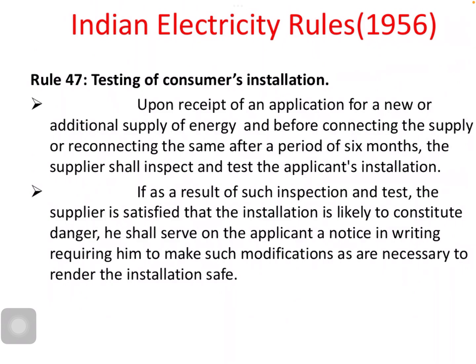Coming to 47, he will be testing the consumer installation. That is, once the application is received, the supplier has to maintain that record which is obtained from the consumer, and in case of inspection, if he is satisfied, he will have to serve on the applicant a written notice requiring that modifications be done, so that the installation is in a safe condition. This is related to the supply and use of energy. So the consumer's installation will be tested by the inspector.